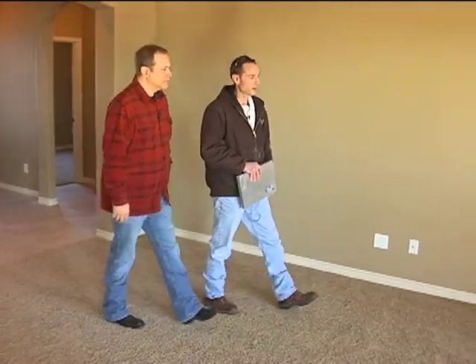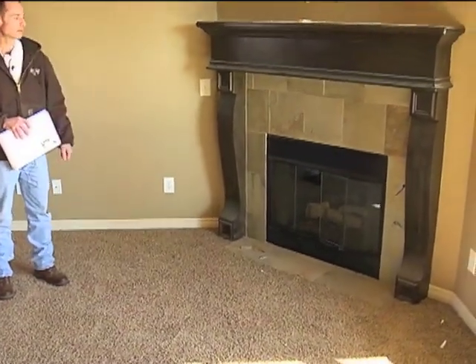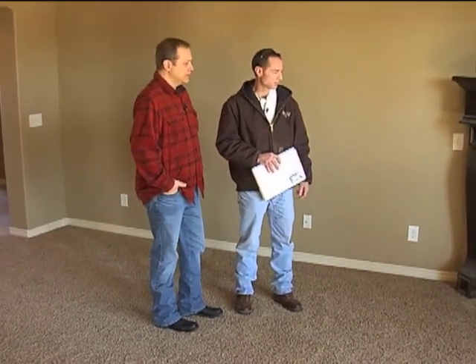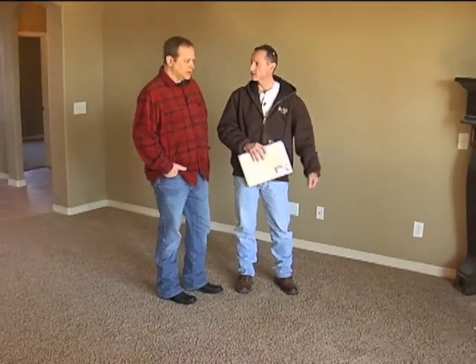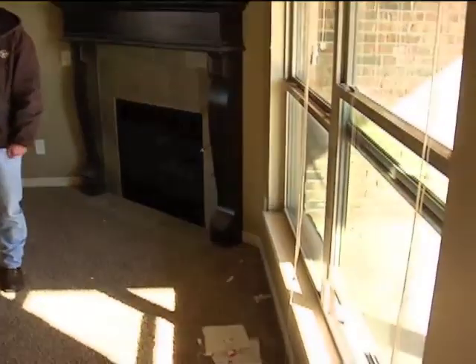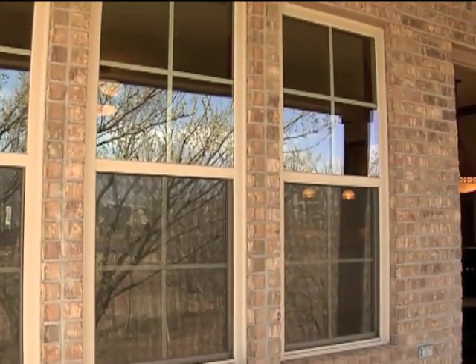This is a manufactured fireplace, and we would verify that the manufacturer's required clearances are maintained. Okay. Gas connections are proper. It has a manual valve so that somebody can quickly shut off the gas if they need to. All of these safety aspects are what you're looking for. Right, absolutely. Big window there. Yeah. There are requirements on windows when they get over a certain size. They have to be tempered, or their proximity to a door can also trigger that requirement.